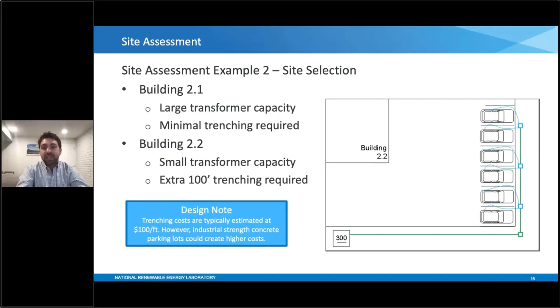And we'll really see that come into play with this second building, 2.2, where a smaller transformer capacity of about 300 kVA is potentially at greater risk of requiring an upgrade from the utility's perspective. And you also look here, the only parking locations that were available in this facility were actually a little bit farther away from where the transformer was. So if we're still going along that route of installing a new electric service, then we're going to need a little bit of extra trenching, probably about an extra 100 feet. This is something you want to avoid at all costs because it is one of the most expensive elements associated with EVSE installation. So based on a couple of analyses, it looks like building 2.1 is probably a better candidate.